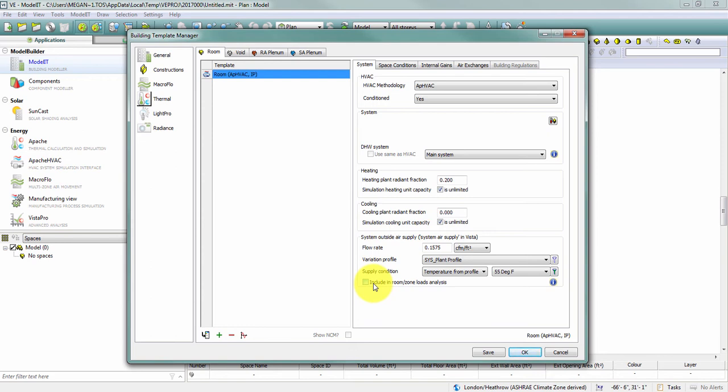And what that means is my ventilation load is going to be a system load and not a room or a zone load. So in a typical VAV system, I don't dump outside air directly into the space. Instead, I condition that outside air at my air handling unit and raw outside air never touches my space, at least through my mechanical system.